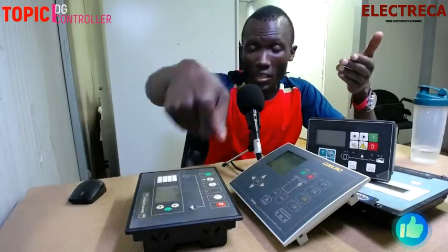If a generator has any advanced problems, it will create an alarm. You will be able to see the alarm, and you're able to reset the alarm. There are quite a number of alarms. There are alarms that you need to reset, and then the generator will work. There are alarms that you need to take action on. For example, if you had an alarm of low coolant level, you need to take action of adding coolant. There are alarms like low voltage alarms, which you can simply reset.